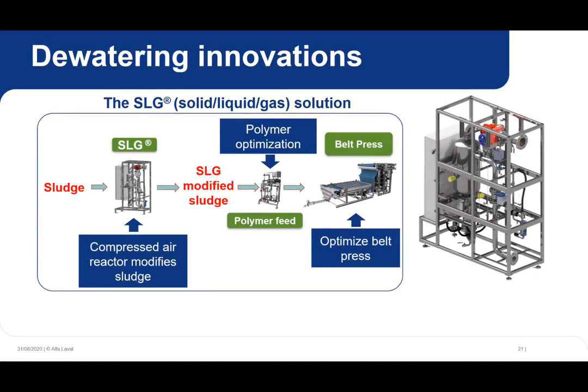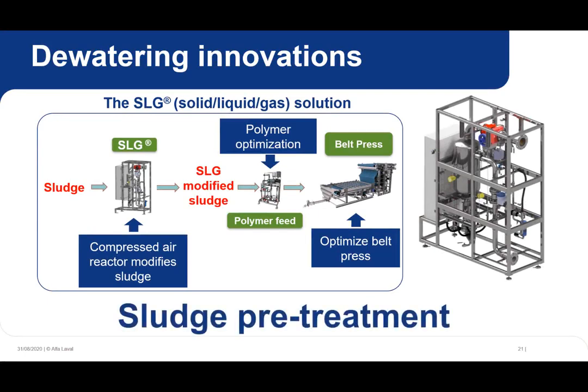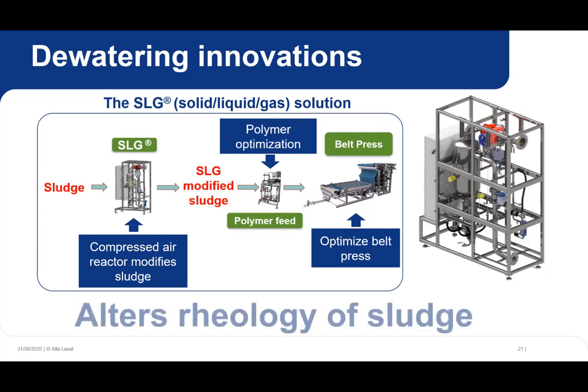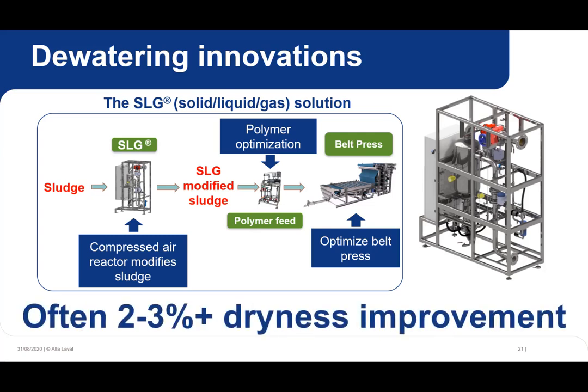Another innovation we're seeing in dewatering involves advanced pretreatment of sludge before it even sees a dewatering device. One such example of that is the Orej SLG. Shown here, its process uses compressed air to modify the actual rheology of the sludge and release water at the cellular level, causing solids in the sludge to float and improve dewatering. Adding this prior to a belt press can often give 2% higher dryness or more, as well as improve polymer use and belt press throughput. Also, the entire device fits in a 3x5-foot space. Alfa Laval has partnered with Orej to bring this technology exclusively with their belt presses in the greenfield and brownfield space.